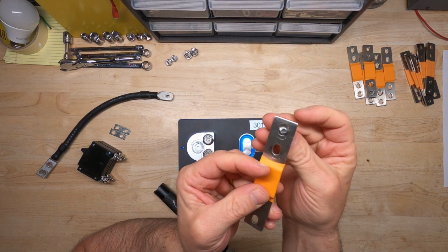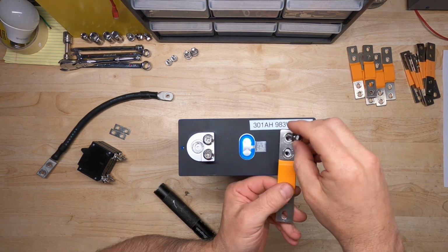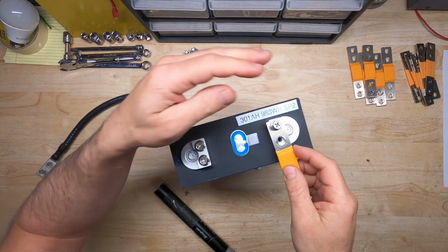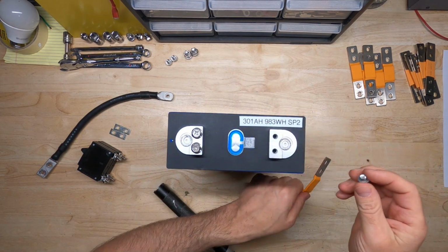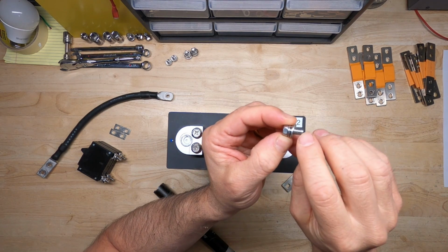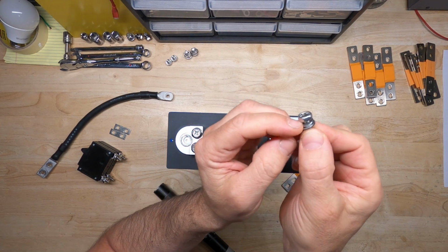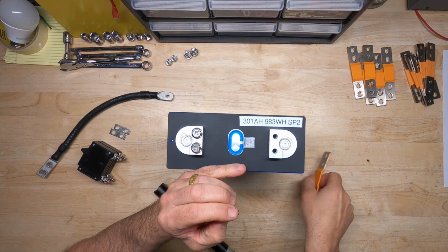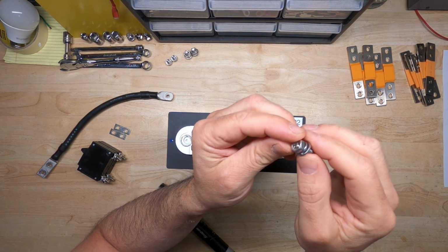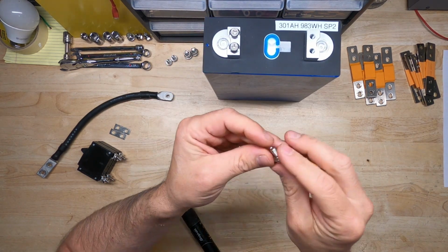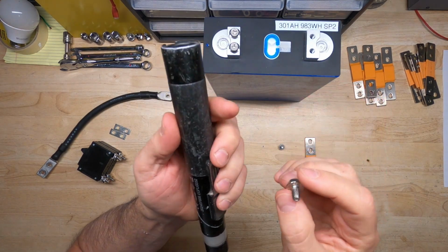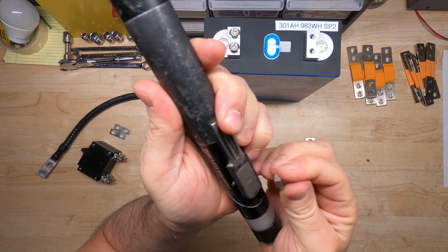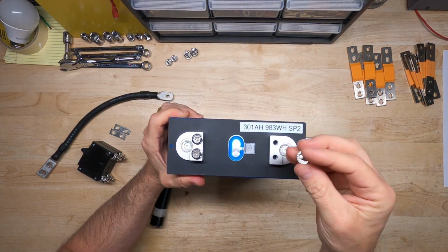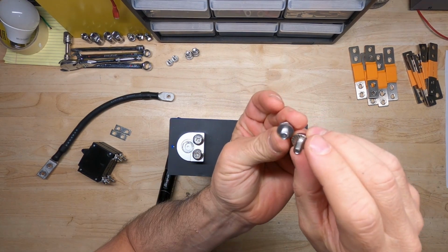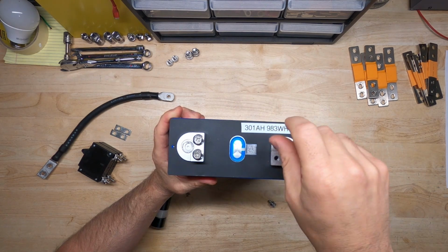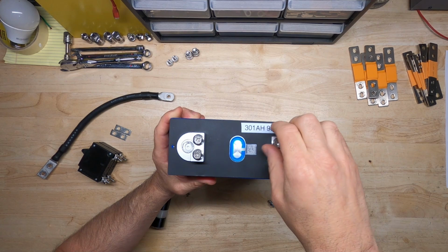if you notice, there's some play in there, right? On the bus bar. So what has to happen, you can see how that moves around like that? So what has to happen is the bolt at high current has to end up taking on some of the current. So the current has to actually flow through the bolt up into the head and then back down through these washers and the lock washer back into the bus bar. And that can create a lot of resistance as well. So those are the two reasons. This one, however, standard bolt, serrated bolt, I think it's zinc, very magnetic, and it's a solid piece, right? So the head is actually more broad, but I think mainly it's the material that the bolt is made out of is what the problem is. So that's a pretty solid connection there.